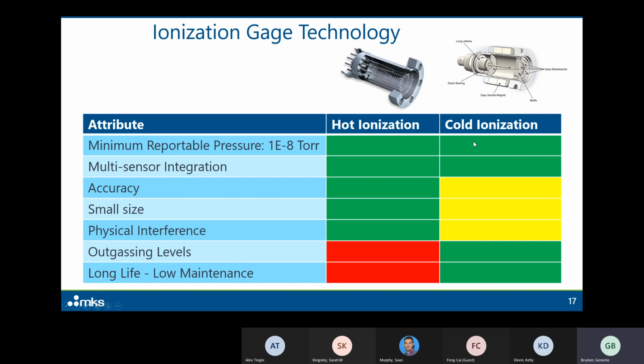We knew that both of these technologies could achieve the minimum reportable pressure of 10⁻⁸ torr. We knew that these two technologies could be used in a multi-sensor integration package; it had already been done. We had done it already, not in this small scale, but in other instruments. We also knew at that point that hot cathode ionization was known for showing better accuracy than cold ionization. So we gave cold ionization a yellow here in the risk department. We knew that hot cathode gauges could be miniaturized. All you have to do is look at our micro-ion gauges, and you'll see you can make very small hot cathode ionization gauges.